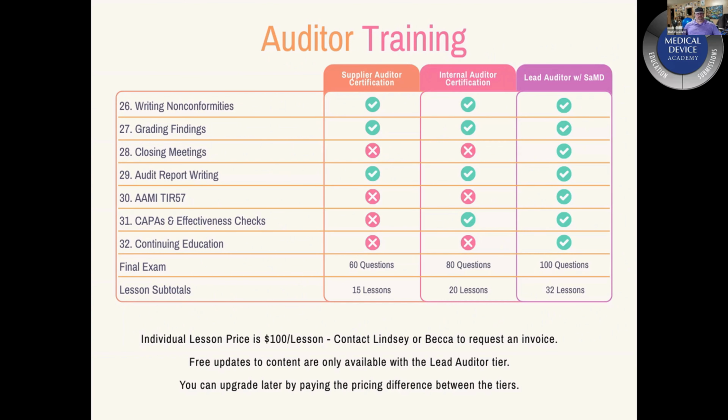The one for software, everybody talks about 62304, but there's actually a more useful standard from a risk management standpoint called IEC 80002-1 that tells you how to apply risk management to software. But then they have a separate one that has a similar number, 80002-2, for software that's used for the quality system.